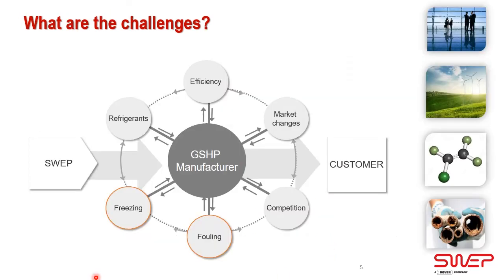Why aren't all heat pumps in the US equipped with a brazed plate heat exchanger? Well, for SWEP to let our heat exchangers give the full benefit to the end customer, we have to go through our customer, the ground source heat pump manufacturer. And surprise, surprise, the heat pump manufacturer has other things on his mind than what heat exchanger technology to use. He's looking at what's the efficiency for this heat pump, where we want to go with that, how is the market changing, what is competition doing, what kind of refrigerants are we going to use. And then there is the fouling and freezing challenge. The fear of fouling and freezing, SWEP has noticed, is the most common reason why a heat pump manufacturer does not use a brazed plate heat exchanger and instead uses the less efficient and heavier coaxial heat exchanger. So SWEP has wanted to attack fear with facts.